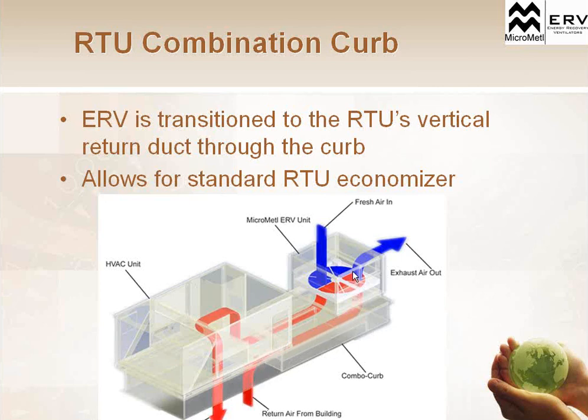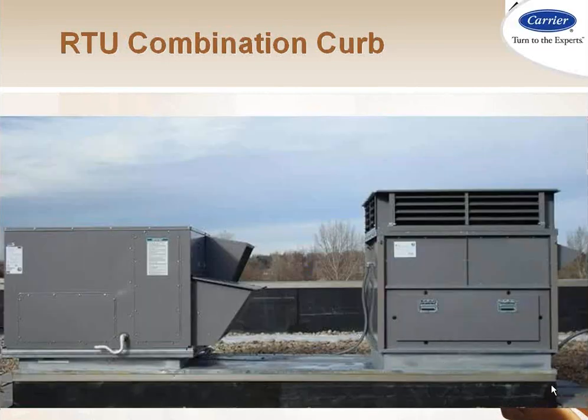So we take return from the building into the roof curb, out through the ERV. That fresh air would come in through the ERV, going into the roof curb, and back into the rooftop unit, or HVAC system itself, and into the building. So that's obviously the most common, the combination roof curb.